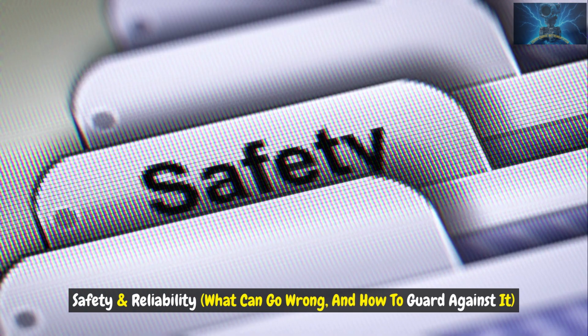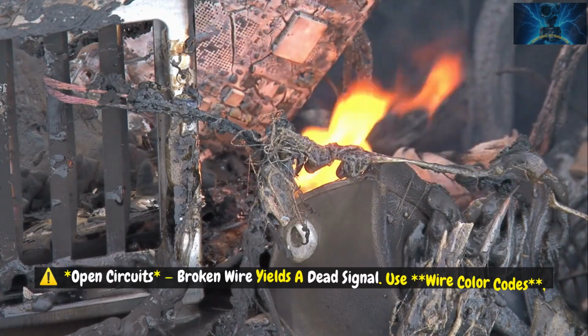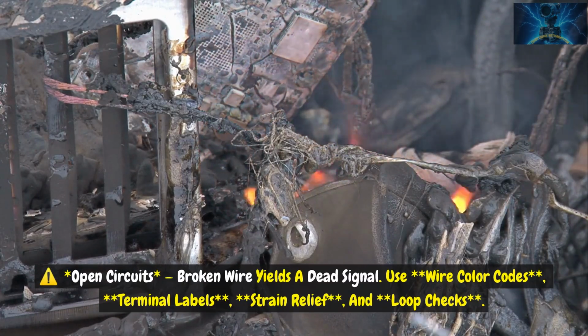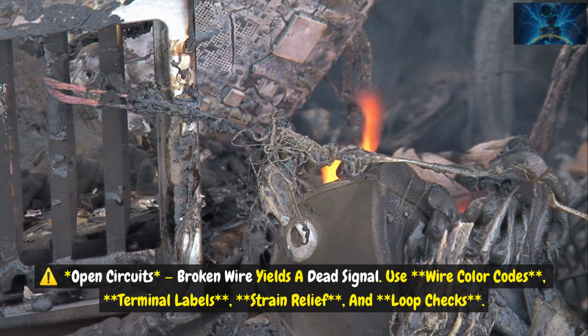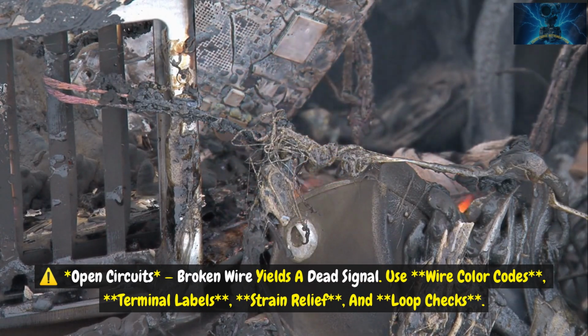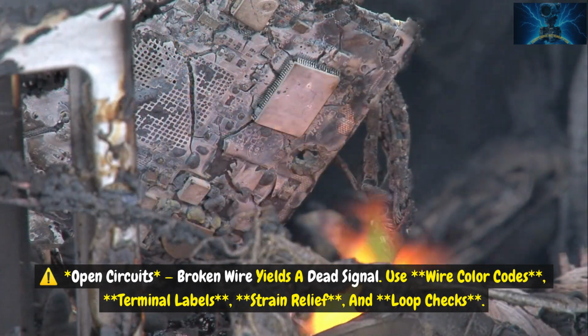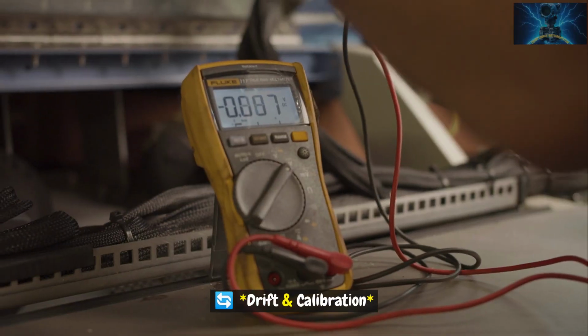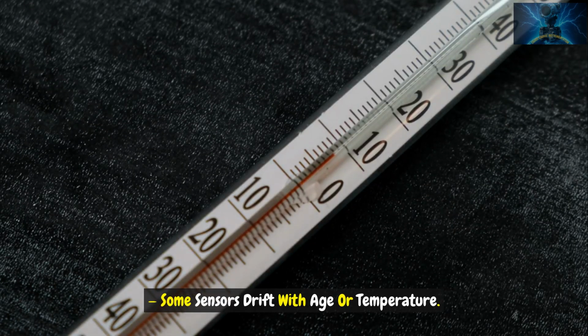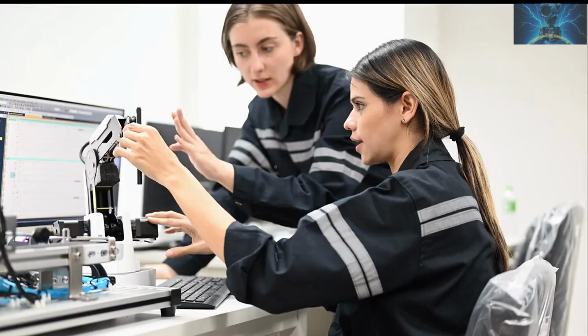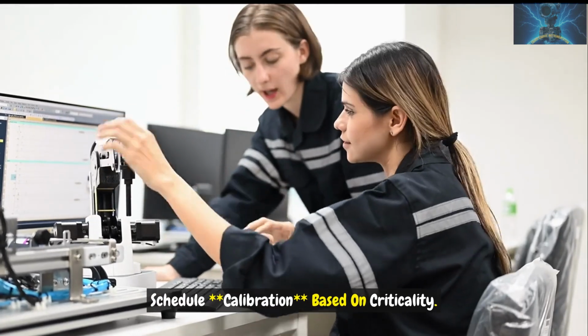Safety and reliability, what can go wrong and how to guard against it. Open circuits. A broken wire yields a dead signal. Use wire color codes, terminal labels, strain relief, and loop checks. Drift and calibration. Some sensors drift with age or temperature. Schedule calibrations based on criticality.